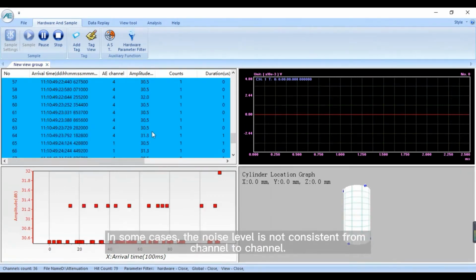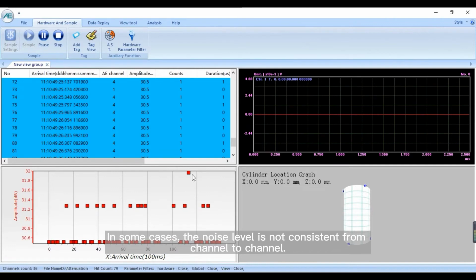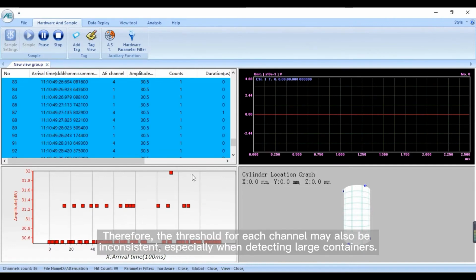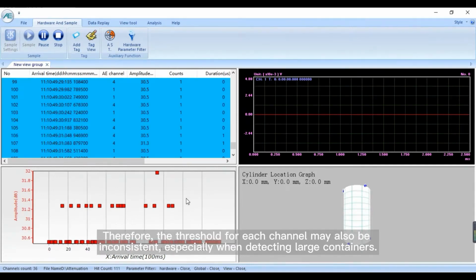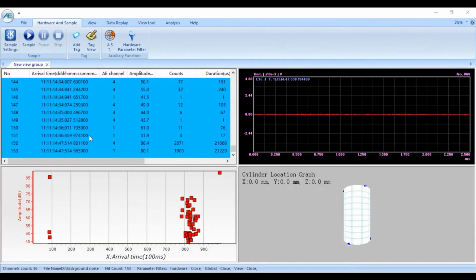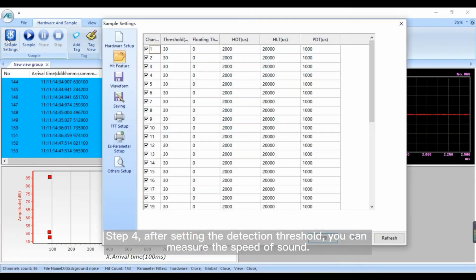In some cases, the noise level is not consistent from channel to channel. Therefore, the threshold for each channel may also be inconsistent, especially when detecting large containers. Step 4. After setting the detection threshold, you can measure the speed of sound.